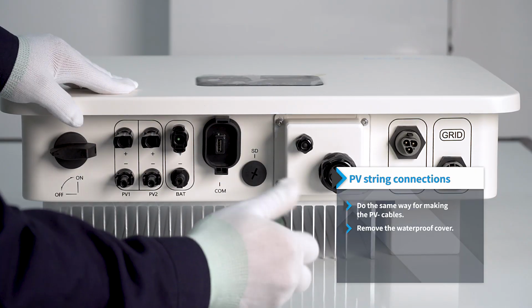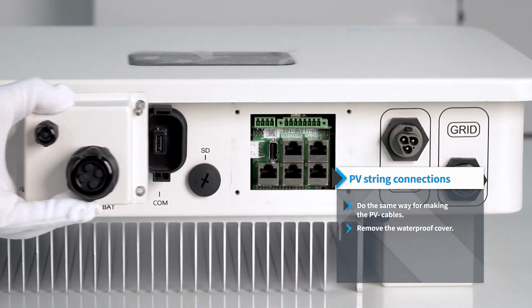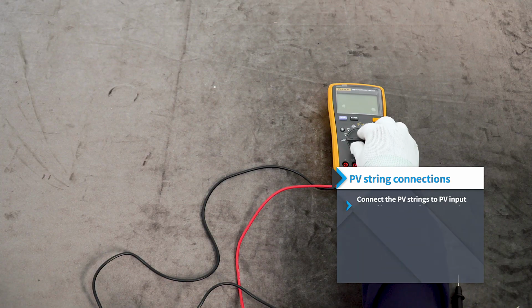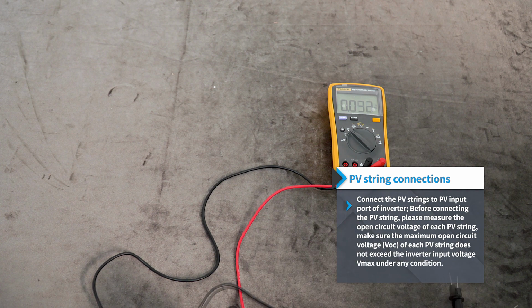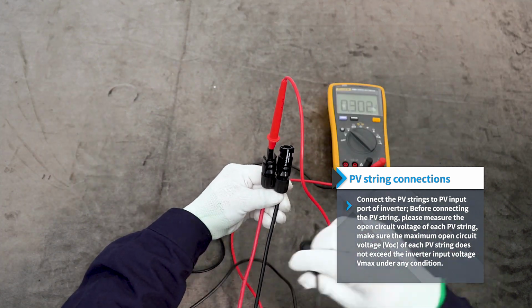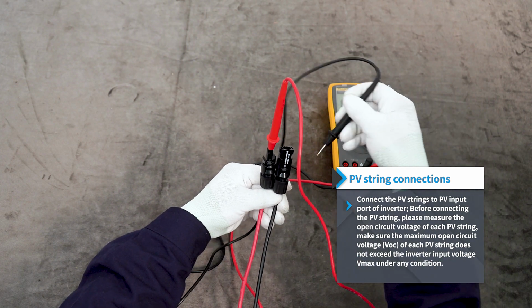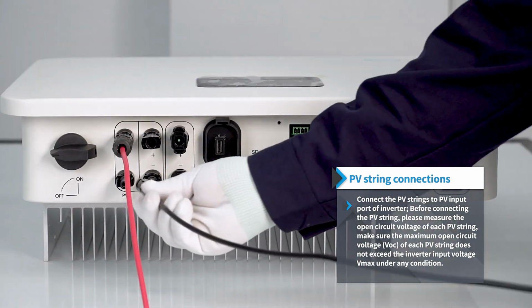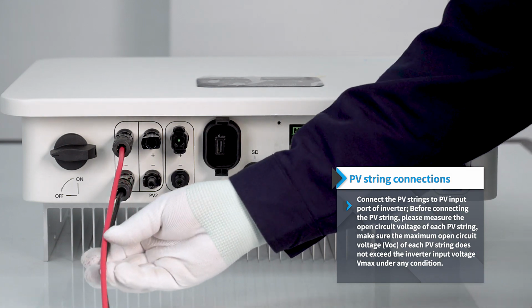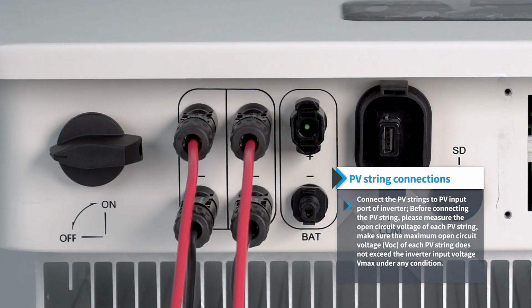Remove the waterproof cover. Connect the PV strings to PV input port of inverter. Before connecting the PV string, please measure the open circuit voltage of each PV string. Make sure the maximum open circuit voltage, VOC, of each PV string does not exceed the inverter's maximum input voltage under any condition.